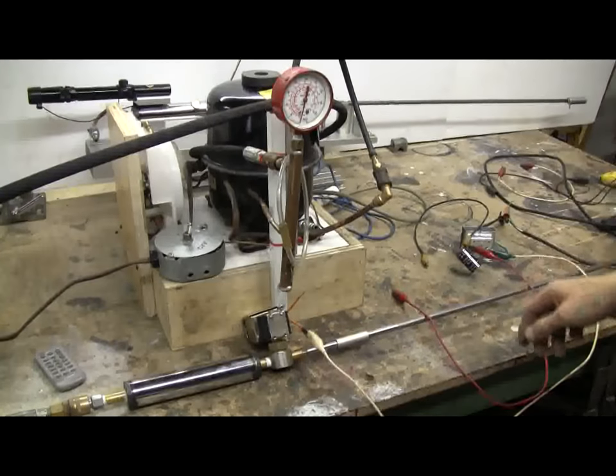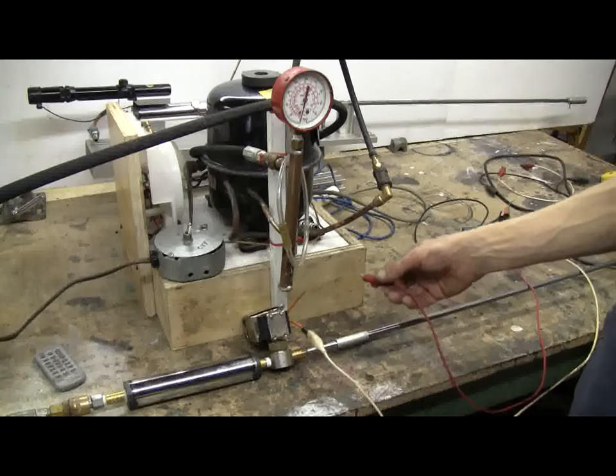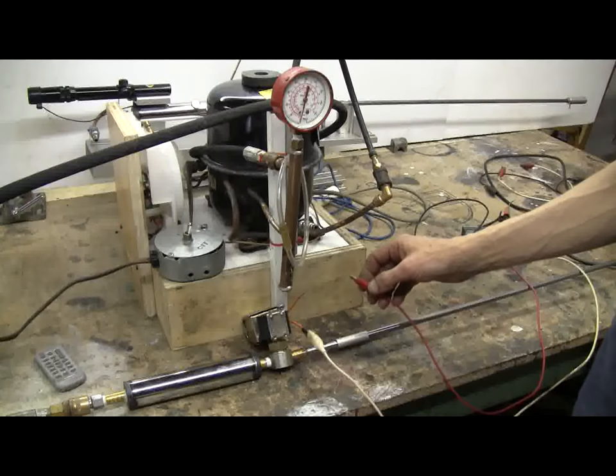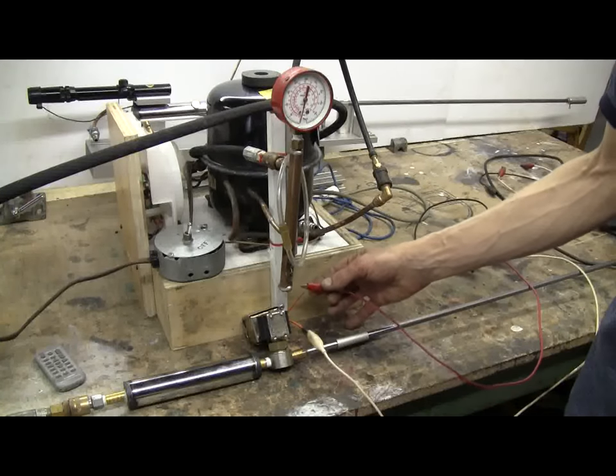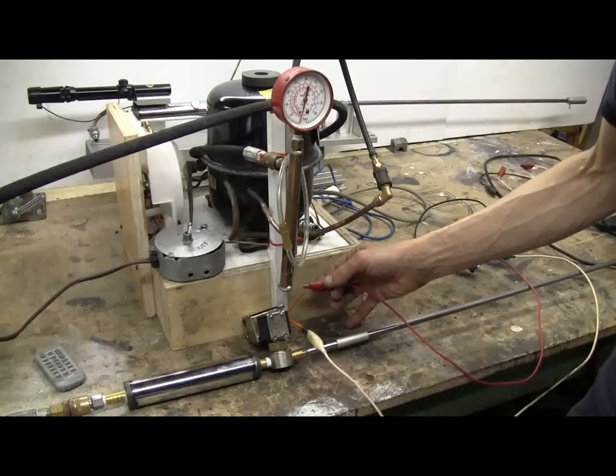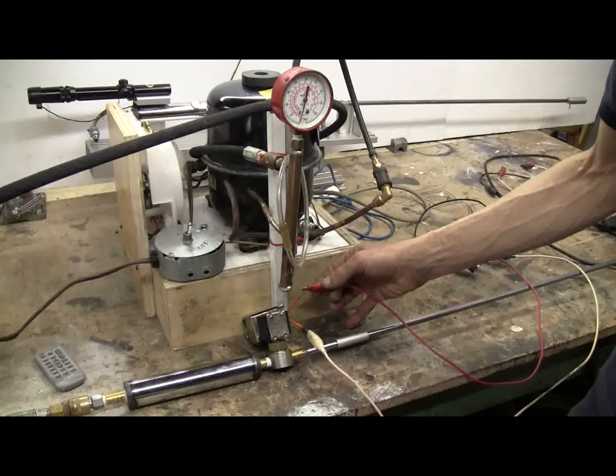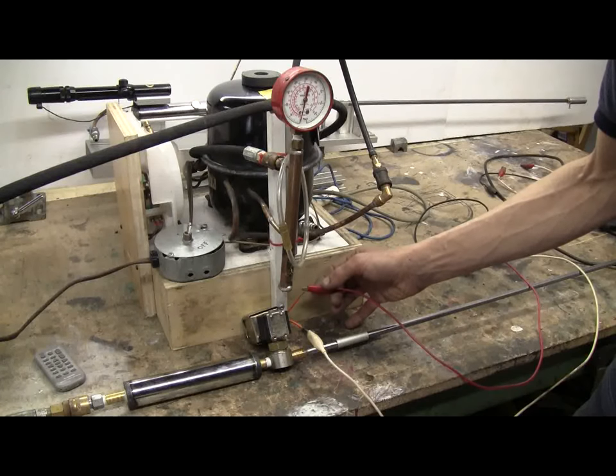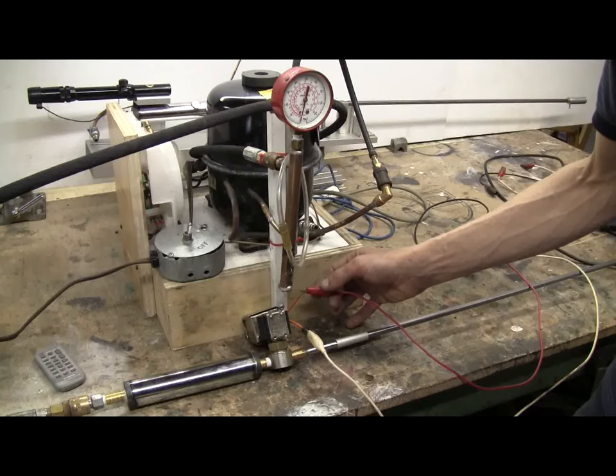Here I've got the power supply set up and running to deliver 24 volts AC, which is what we're supposed to run the 24 volt solenoid on. When I complete the circuit here you should be able to hear the solenoid clicking open and closed in the video. There is no air pressure applied right now, this is just a valve test. The valve is opening quite well at zero pressure.